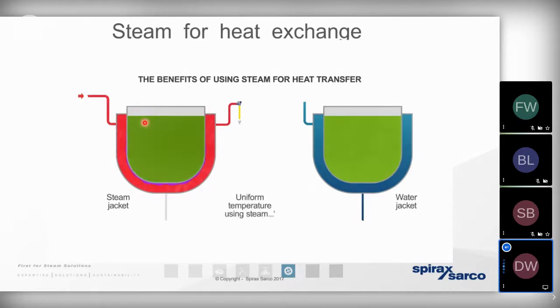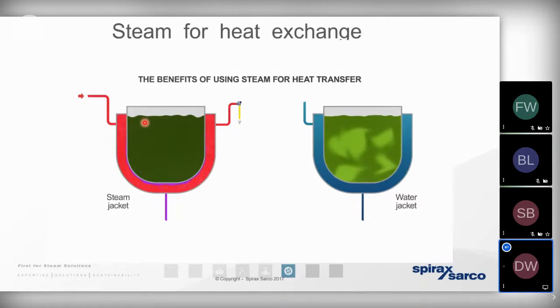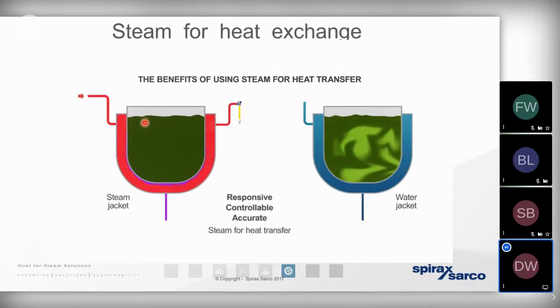We also know that steam's got a very, very high energy content and a very high heat transfer coefficient. We sometimes refer to that as a U value, or a speed of heat transfer. And we also know that steam gives up its heat energy at a constant temperature, and it uses all of the heat transfer space evenly, meaning we don't get cold spots or spoilage. And it means we can bring the temperature of the process up to the required set point by nothing more than manipulating the steam pressure.